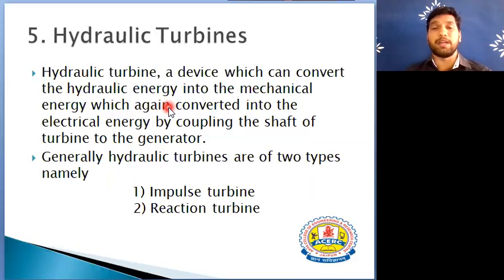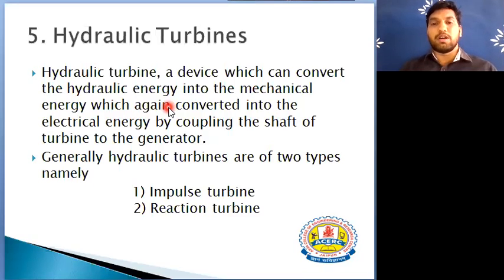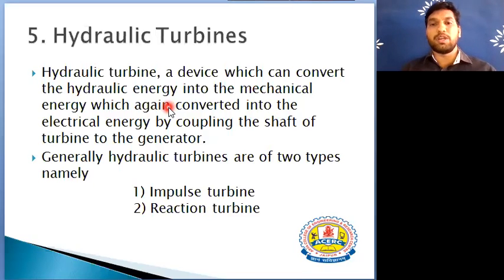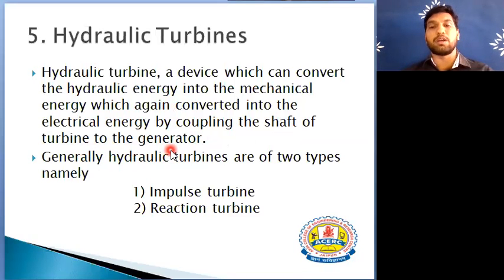Next, the hydraulic turbine is one of the most important parts of a hydroelectric power plant, which is coupled with a generator. The water stored in the reservoir has potential energy. This potential energy is converted into kinetic energy when the water comes out from the penstock through a nozzle or jet. When the water strikes the turbine, the kinetic energy is converted into mechanical energy. The turbine rotates and this mechanical energy drives the generator, producing electric energy. So the hydraulic turbine is a device that converts hydraulic energy into mechanical energy, which is then converted into electrical energy by coupling the turbine shaft to the generator.